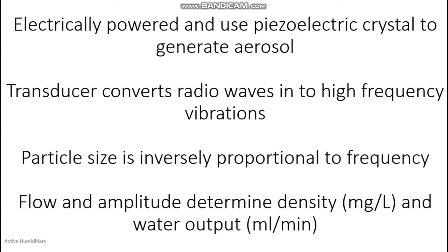Ultrasonic nebulizers are electrically powered and use piezoelectric crystal to generate aerosol. The transducer converts radio waves into high-frequency vibrations. The particle size is inversely proportional to frequency. And flow and amplitude determine the density in mg per liter and water output in milliliters per minute.